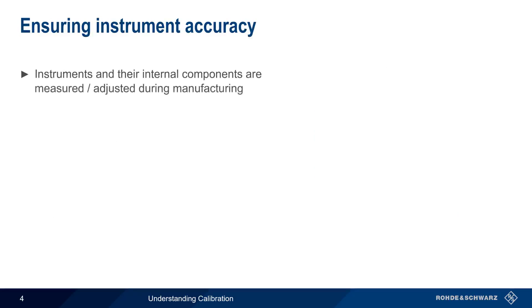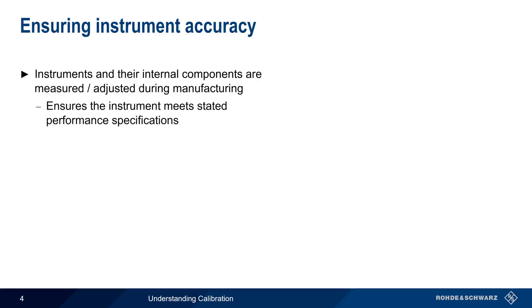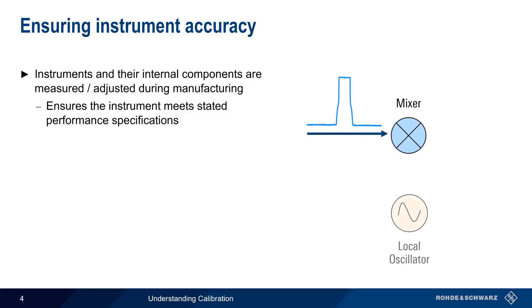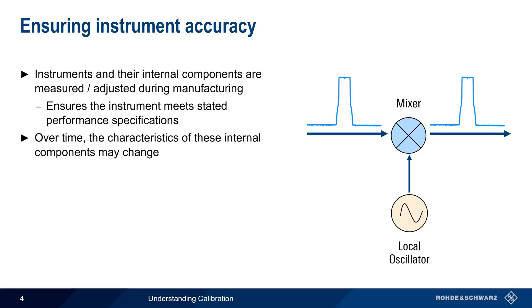The internal components of an instrument are measured and adjusted as part of the manufacturing process, ensuring that the newly manufactured instrument meets its stated performance specifications. For example, in the case of a spectrum analyzer, the local oscillators should have a high level of frequency stability in order to prevent distortion of the measured signal during downconversion. However, over time, the characteristics of these internal components may change.